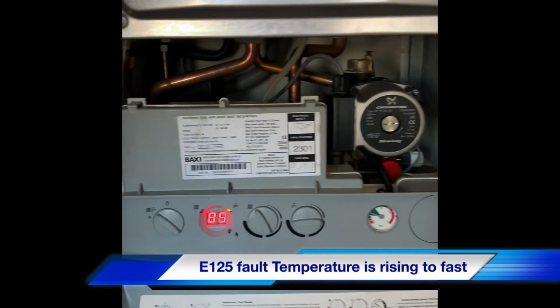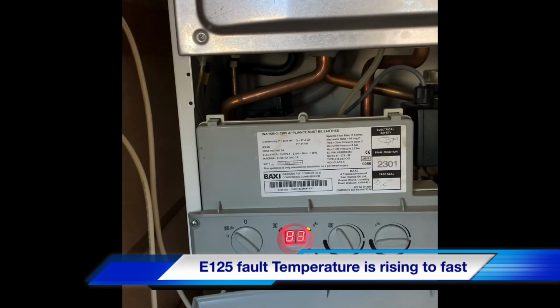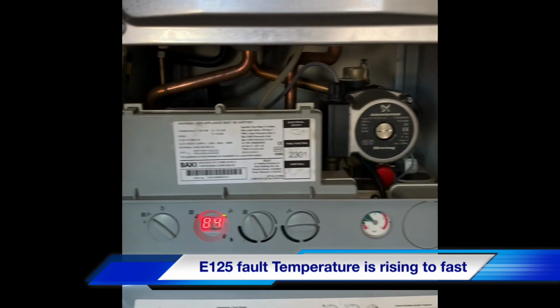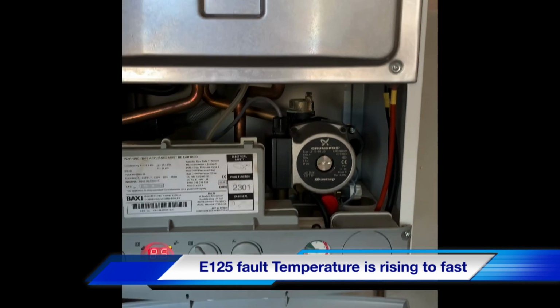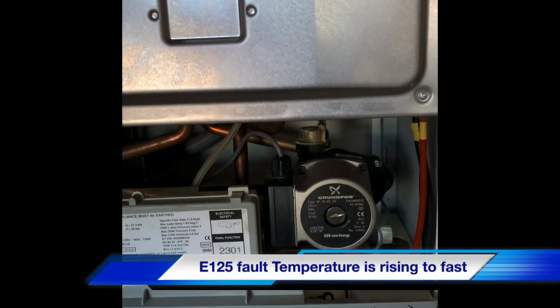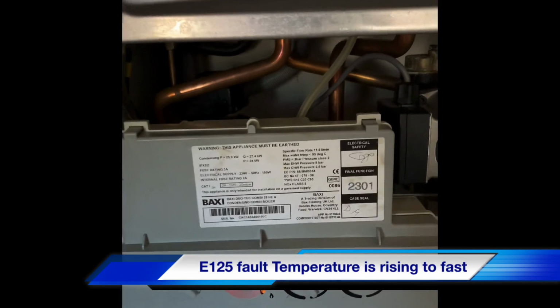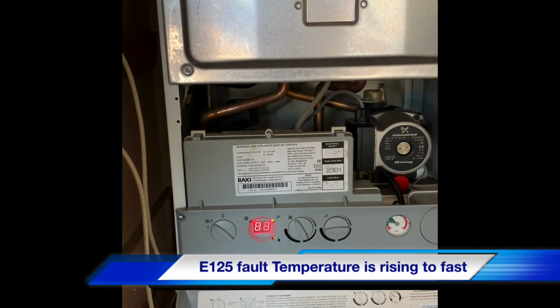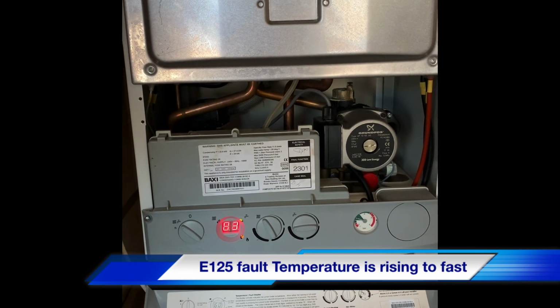From my experience, I generally find that's a plate heat exchanger on this boiler as opposed to a pump problem. These are quite reliable boilers, I find. It's usually down to water quality, so we'll do some investigating and get back to you.